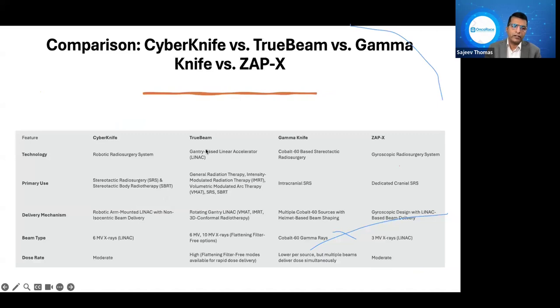So let's go for the comparison of these systems more specifically. If you look at the technology, the CyberKnife uses a robotic system and the TrueBeam uses a gantry-based linear accelerator. Here we could see the Gamma Knife is a cobalt-60 based stereotactic radiosurgery and ZAP-X is a gyroscopic radiosurgery system. CyberKnife is primarily used for stereotactic radiosurgery and stereotactic body radiotherapy. And TrueBeam is for general radiation therapy, intensity modulated radiotherapy, volumetric radiotherapy, and for SRS and SRT, whereas the Gamma Knife and ZAP-X are dedicated cranial SRS devices.